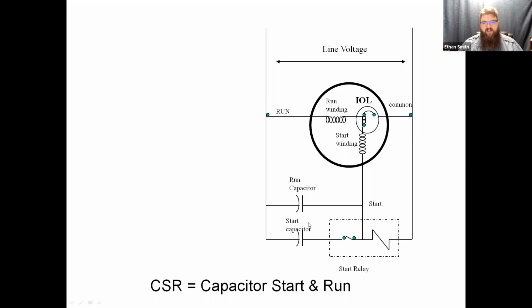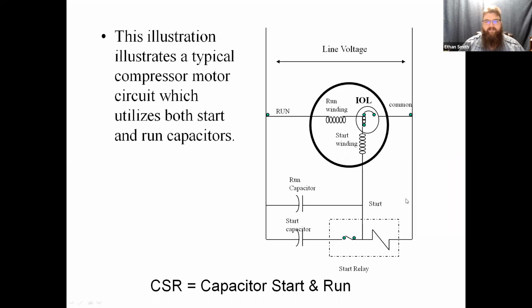That's why occasionally you'll see start capacitors blow up when you have a locked compressor, because what's happening there is we're keeping that start capacitor engaged, trying to get that motor to spin, but it never starts spinning. These start capacitors are generally not meant to be in circuit for more than a second or two. And so they start to break down when they're constantly engaged on something like a locked rotor compressor. So occasionally you'll see the little relief port on those things blow off, and the inside of your compressor or your electrical cavity will be covered in this black or white goo that's blown out of that capacitor.